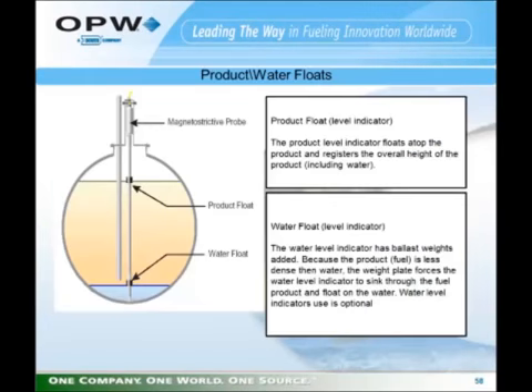So the product and water floats are, as you would understand them to be, the product floats on top of whatever product might be in the tank. The water float floats on top of the interstice between any product and any water that might be in the tank. The water float has a weight ballast on it so that it will sink through product but not sink through water.